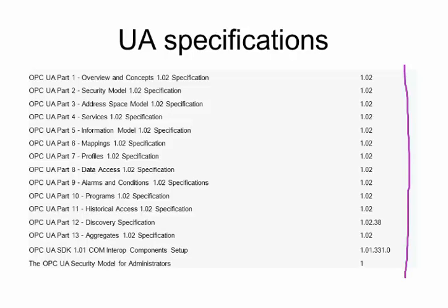UA is about shifting away from being Microsoft-centric. UA is very much based purely on IP. It's also updated to understand security certificates and be designed to run in a secure manner, over the open internet, and get away from a bunch of the issues that were inherited from the Microsoft DCOM approach. So just be aware, these are the standards for UA. So it stands for Unified Architecture.